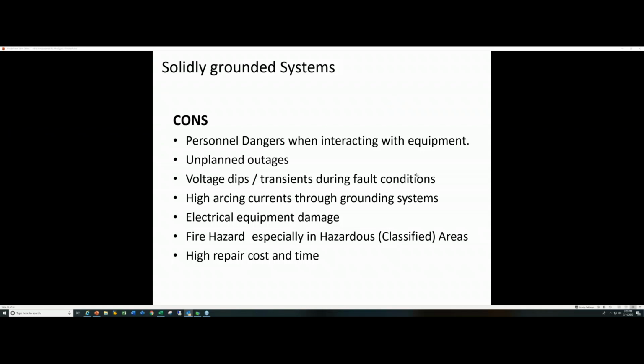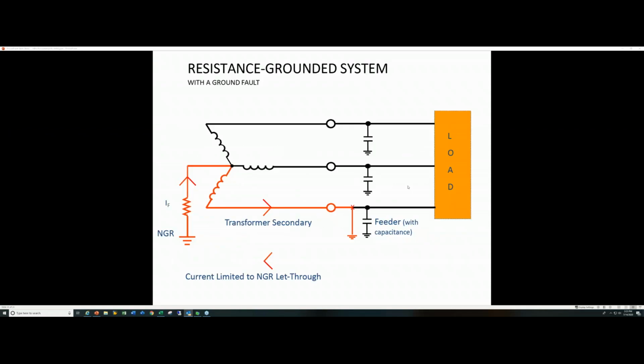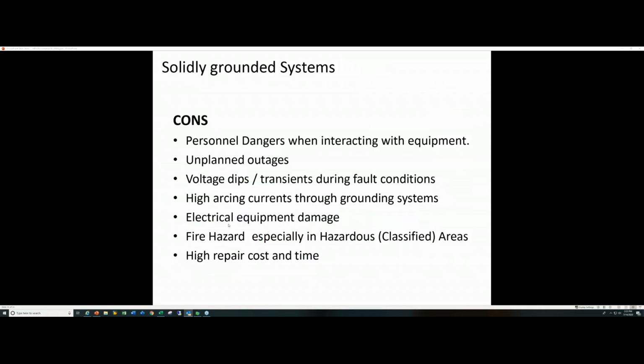You will have voltage dips, transients during fault. You imagine that 30,000 amps coming down the line under a faulty condition, it's pulling your whole bus system down, everything. High arcing currents. You have electrical equipment damage. You all have seen that if you've been in the industry for very long. When a fault happens on a solidly grounded area, it's pretty impressive, even when you're coordinated. Fire hazards, another one. Remember, you're introducing that arc, that incident energy of that 30,000 amps, let's say, in the case of that, and you've got 30,000 degrees. You're apt to catch things on fire.